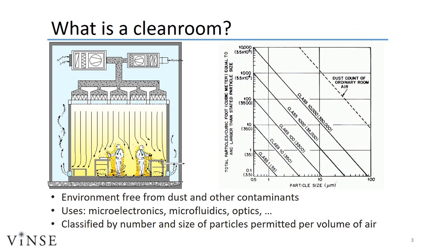Due to the nature of where contaminants settle, it is advised that all work be conducted at about waist height. While the process space is maintained within classification, the floor may not be, and any dropped samples should not be considered clean. In addition to filtration, to prevent particulates entering the space when a door opens, the clean room is maintained at positive pressure, causing air to flow from clean to dirty.